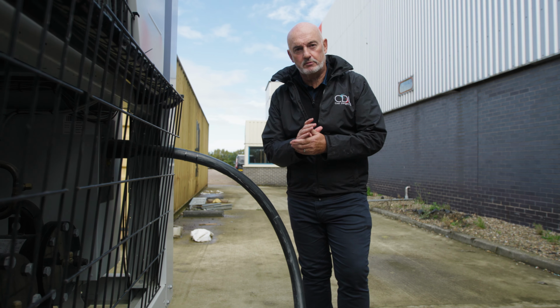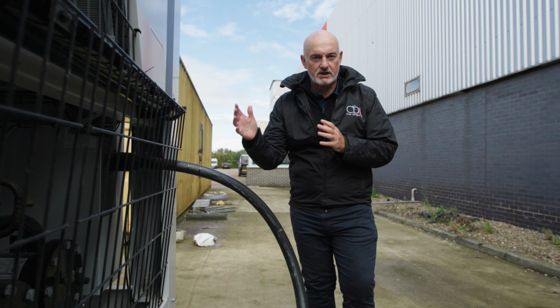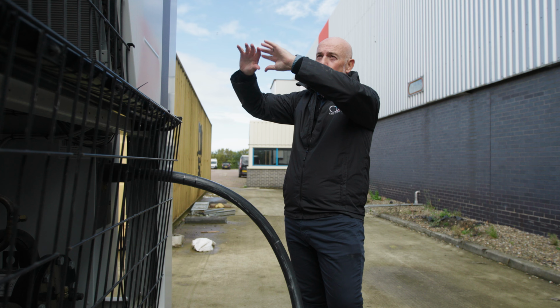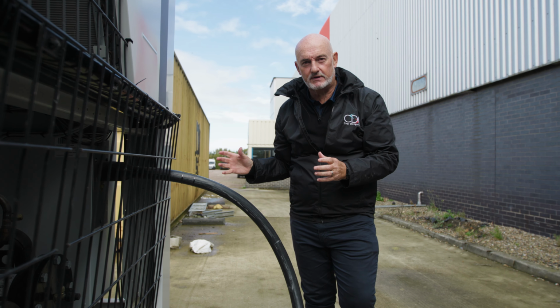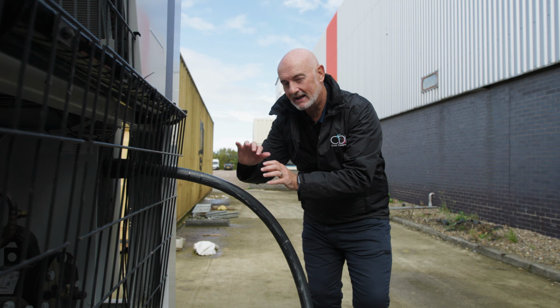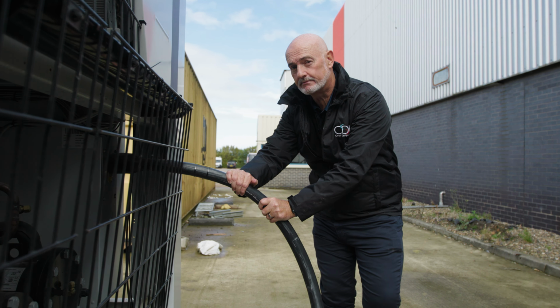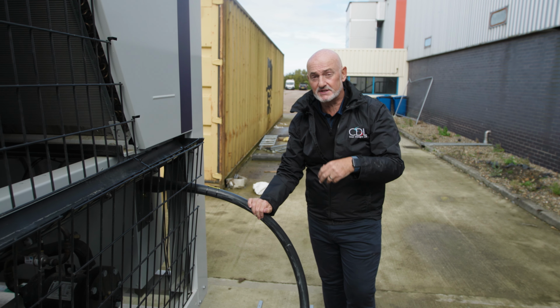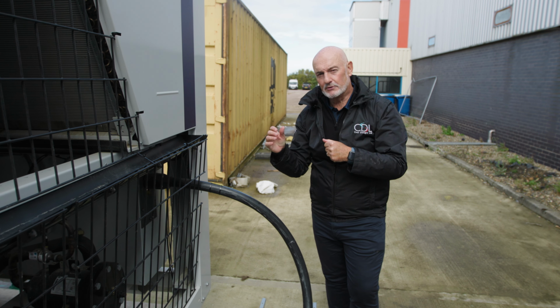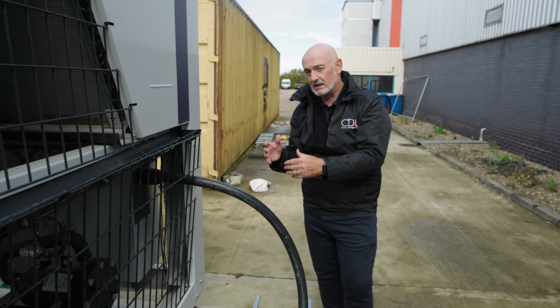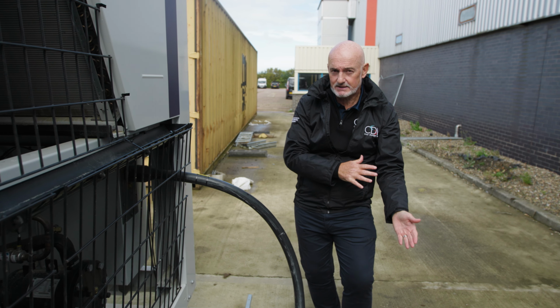The coefficient of performance is based on a ratio between how much this gorgeous machine can absorb out of the atmosphere compared with how much power it actually absorbs to do so. So again, if I use a kilowatt as an example, a kilowatt input to make the compressors go around versus how many kilowatts can be drawn out of the air is the coefficient of performance, the COP. Now the COP, or the energy efficiency, tails off the colder it gets.